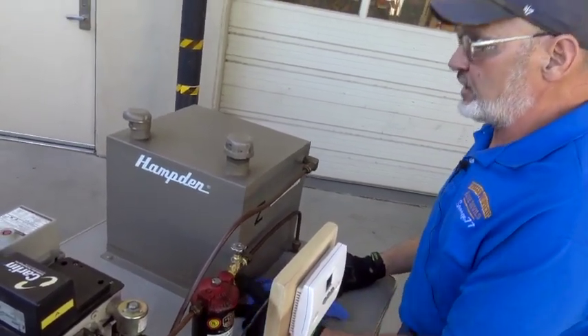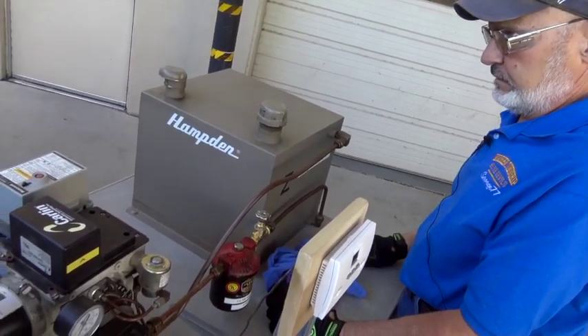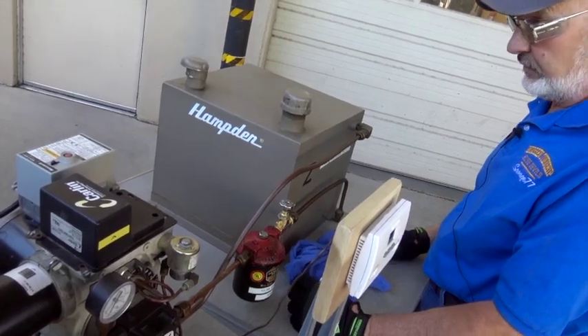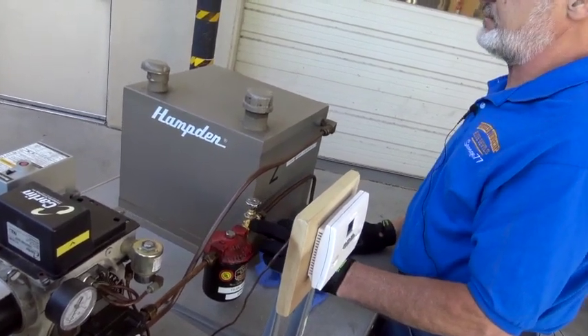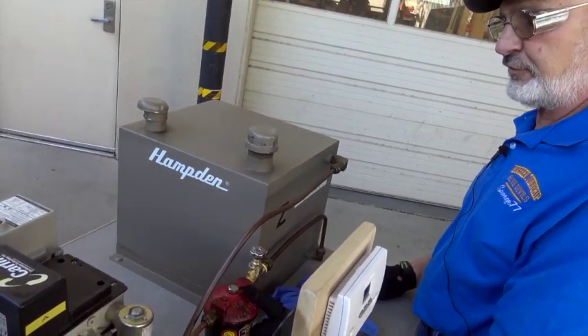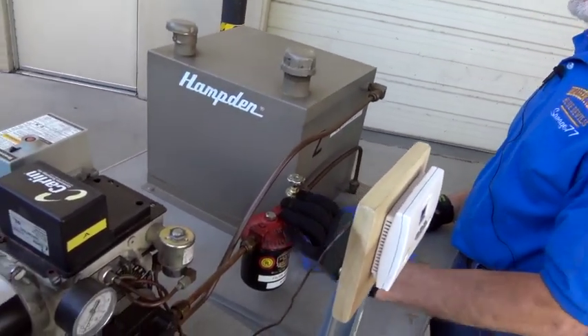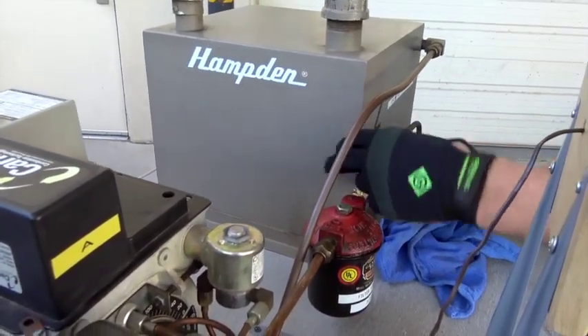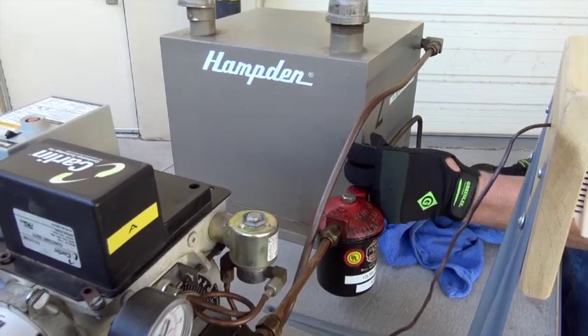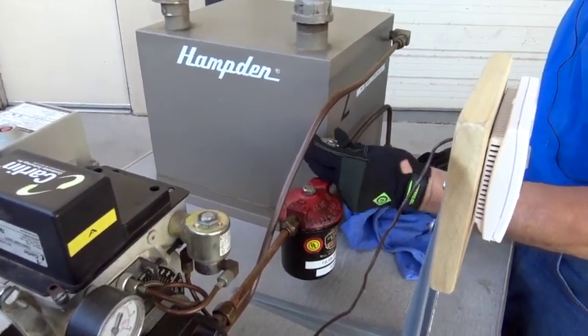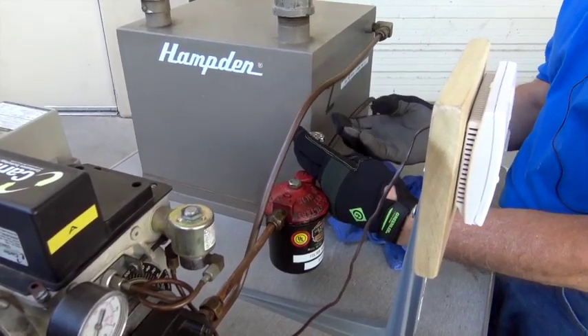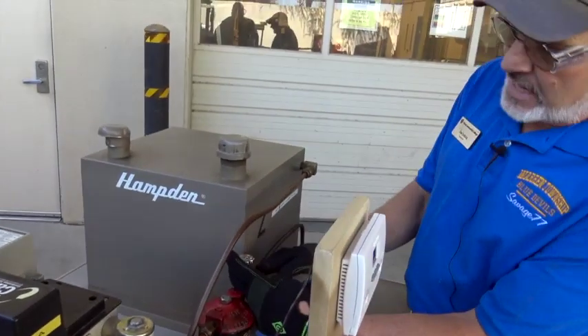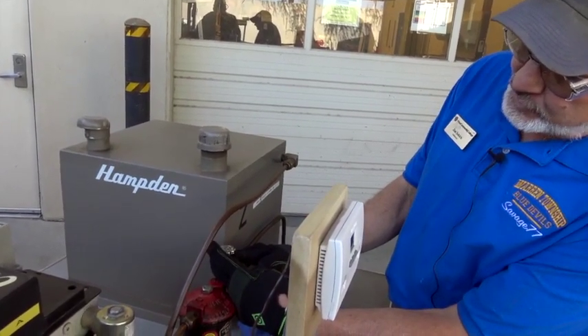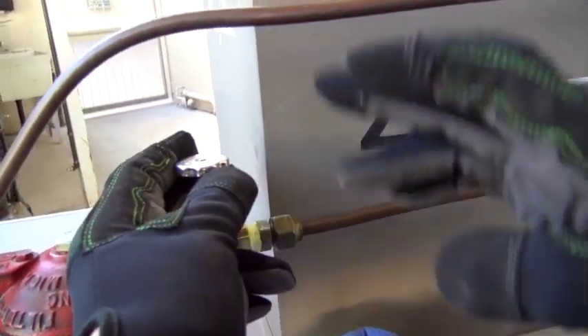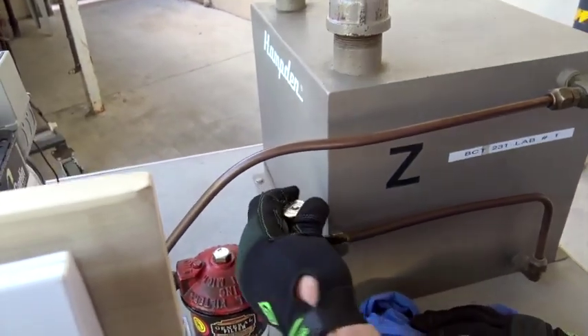Now this is the most misunderstood item on this burner and all gas oil-fired burners. It's a special safety valve. What it is, if this fuel line gets too hot, about 165 degrees, let me take this off, I'll show it to you. As you can see, I can go counterclockwise and back it all the way out like this. It will open the valve. Now, as you can see, it doesn't operate like a regular hand valve. It's got a soft solder sleeve in there. If it gets too hot, it's going to melt and force that spring to close.